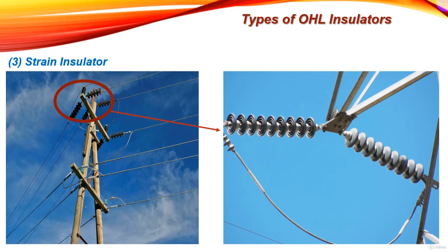Strain insulators are used at angle towers and at road crossings, and they are placed in a horizontal plane. If the tension in the conductor is very high, two or three strings of insulators can be used in parallel to withstand the high tension. Those are the three types of overhead line insulators — pin type, suspension type, and strain insulator — each suited to different voltage and mechanical conditions.